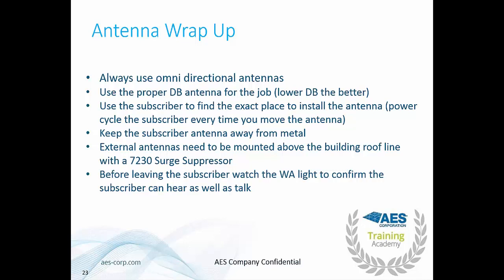Keep the subscriber away from metal. External antennas need to be mounted above the building roofline with a 7230 surge suppressor. Remember, this is to protect the building, not the customer's equipment. Also, before leaving the subscriber, watch the WA light to confirm the subscriber can hear as well as talk.